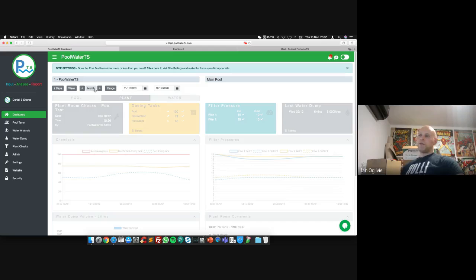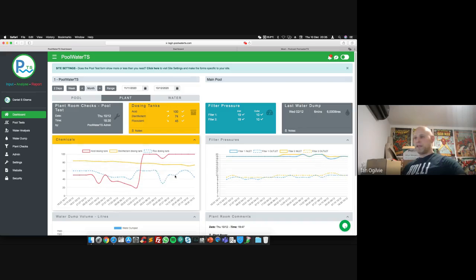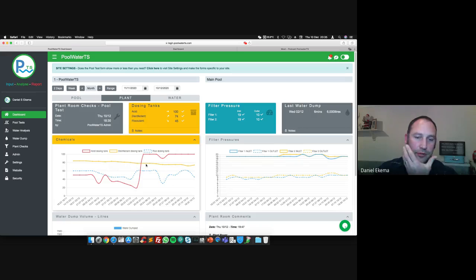Then you're also thinking about busy times, not so busy times. So you can see there the mapping of how full the day tank is, and obviously the red line shooting up there, they've refilled the acid tank. Yeah, definitely. And obviously the chlorine and the flock as well. So you can obviously see those over a period of time to see how they're going down. Plan, as you said, your costings for the future in terms of when you need to order as well.